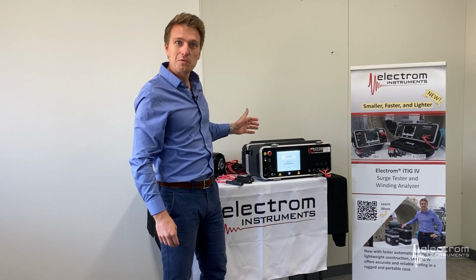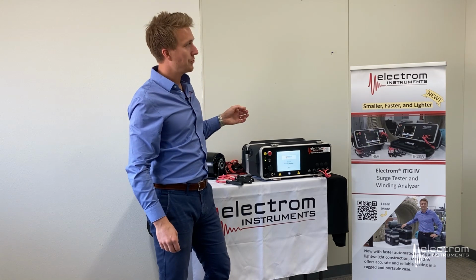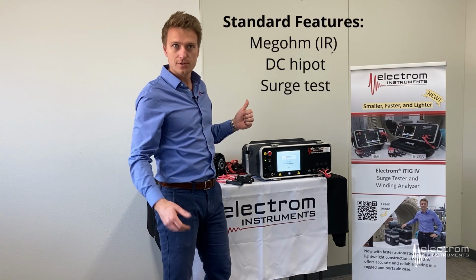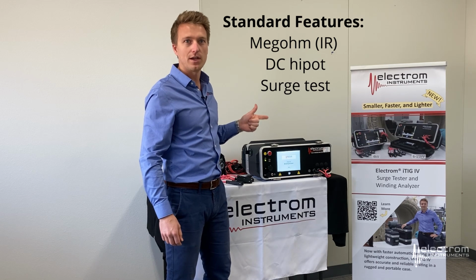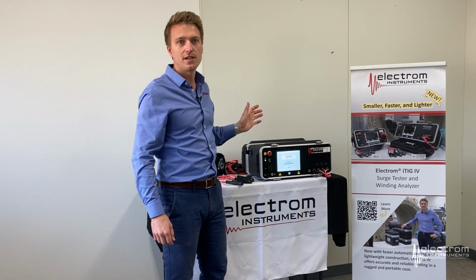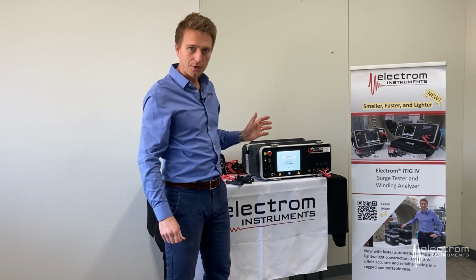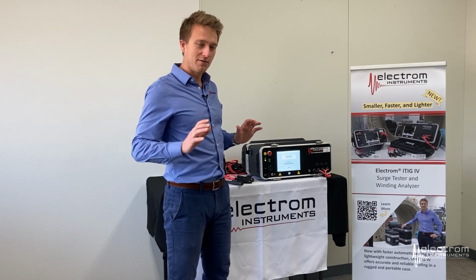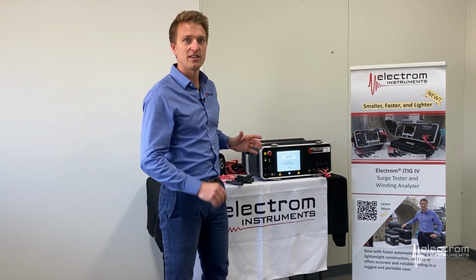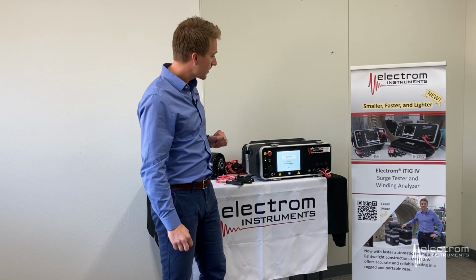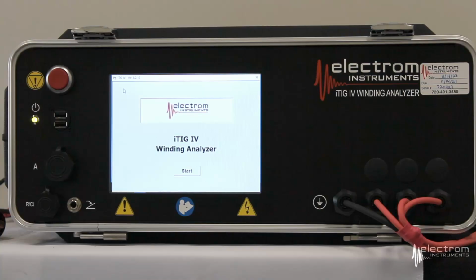This is the iTIG 4 Model A. The Model A includes Megohm, insulation resistance, DC Hipot, and the surge test. No data save, no reporting, but a very powerful tool to check the health of the insulation system. This is a 12 kV version.